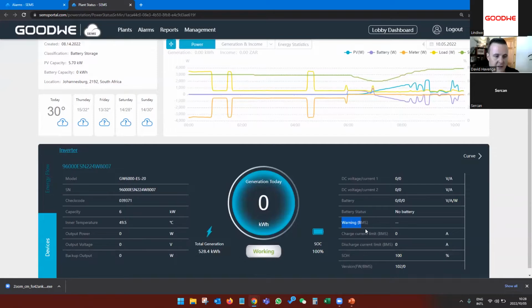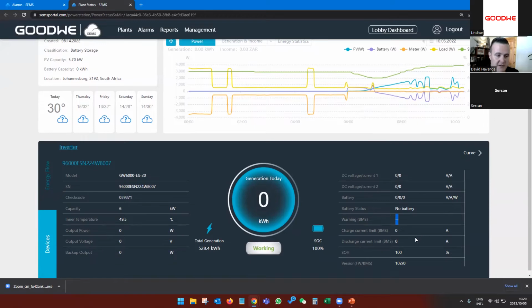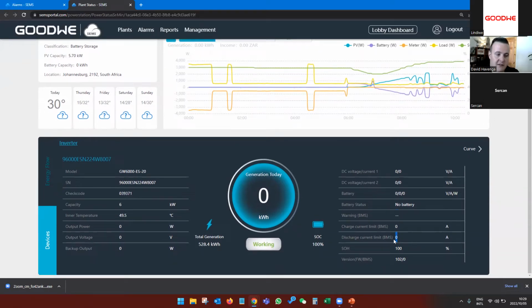And then next we have warning, charge current limit, and SOH. These values are dynamic values from our battery BMS, and they will always change based on the BMS's requirement. So normally when there's no issues, you'll see normal from the BMS. If there's a warning or alarm, you'll see that pop up here from the battery side. The charge current limit and discharge current limit.